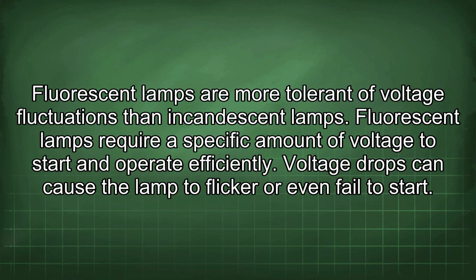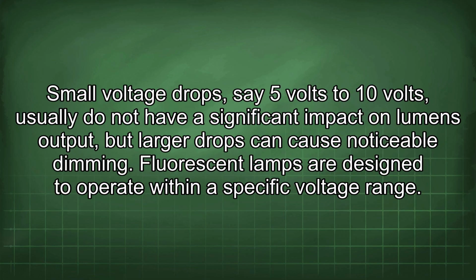Fluorescent lamps are more tolerant of voltage fluctuations than incandescent lamps. Fluorescent lamps require a specific amount of voltage to start and operate efficiently. Voltage drops can cause the lamp to flicker or even fail to start. Small voltage drops, say 5 volts to 10 volts, usually do not have a significant impact on lumens output, but larger drops can cause noticeable dimming.